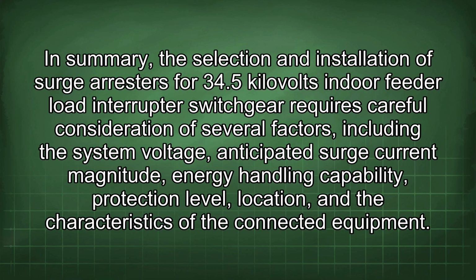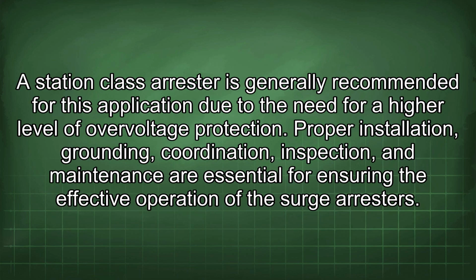In summary, the selection and installation of surge arrestors for 34.5 kV indoor feeder load interrupter switchgear requires careful consideration of several factors, including the system voltage, anticipated surge current magnitude, energy handling capability, protection level, location, and the characteristics of the connected equipment. A station class arrestor is generally recommended for this application due to the need for a higher level of overvoltage protection.